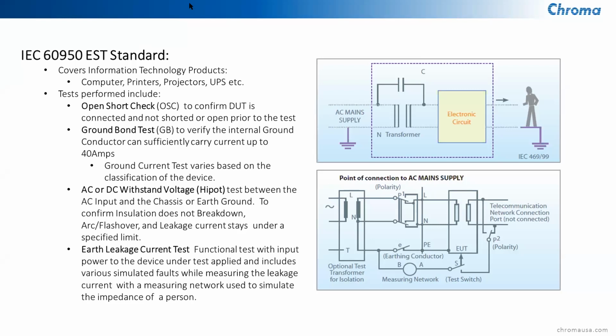The other test is ground bond testing. We covered that briefly. This is a way to ensure that your internal ground conductor can carry sufficient current. The ground conductor has to be capable of handling the amount of current that the device would see if there was a short between the input power to ground. AC/DC hipot, we covered that briefly too, and that would be if there was an insulation breakdown that would cause current to flow back through the earth ground, and that also would cause a problem with the leakage current that could cause a shock hazard.